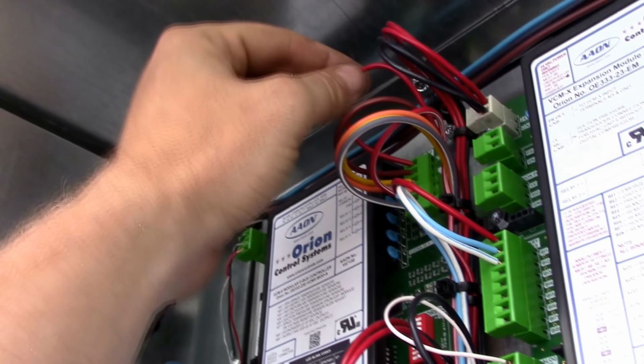Next, we're going to cut this wire in half. This is our new transformer that we put in, and we wired it up right here. You can see this connector here and this connector here. This is 208 volts right here, single phase. So we've got a 208 volt single phase setup there, and then this is the main power coming in. This is all the electric heaters, all of them. Every one of the fuses goes for the electric heaters. There are 6 total heater contactors in this unit, and they're 50 amp contactors under full load amps.